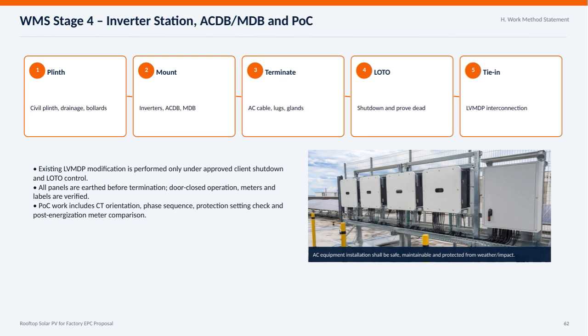The point of connection work also includes checking CT orientation, phase sequence, protection settings, and comparing meter readings after energization to ensure system accuracy. Throughout the installation, the AC equipment must be installed with safety, maintainability, and protection from weather and impact firmly in mind, so the system remains reliable and secure over time.